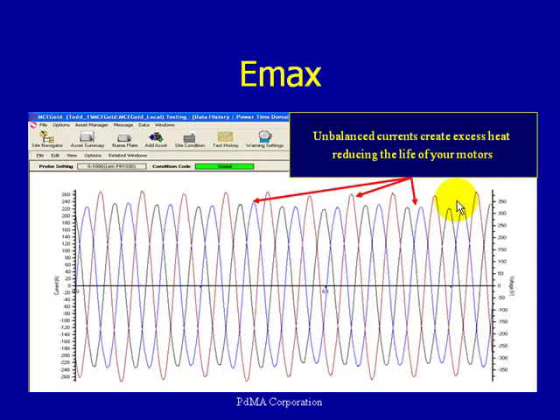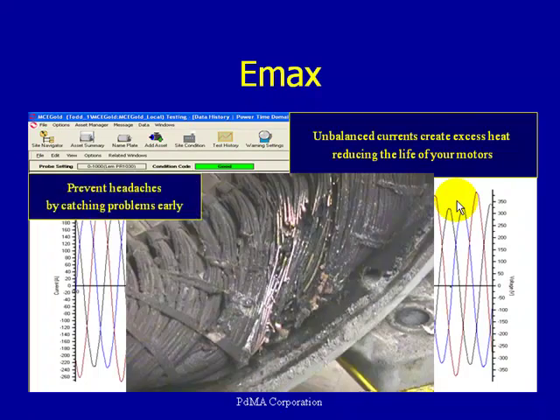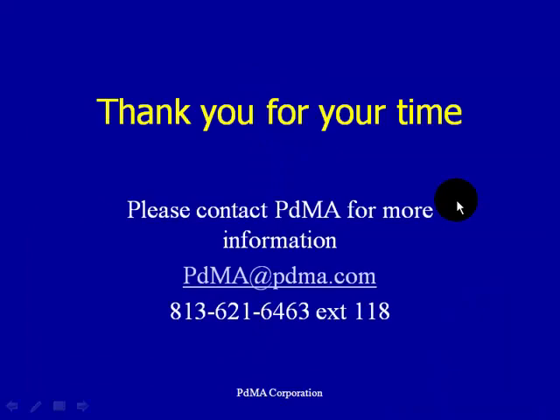Unbalanced currents create excess heat, reducing the life of your motors. Excess heat lowers insulation life and thus reduces overall motor life. Catching these problems early prevents costly failures. To recap: motors with high resistance connections — identified by high resistive imbalance on the MCE test or high current imbalance on the Emax test — are running at reduced efficiency, costing more to operate, and potentially suffering shortened insulation system life due to excess heat.